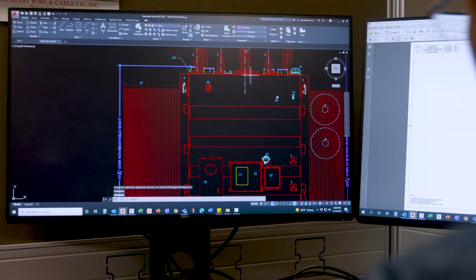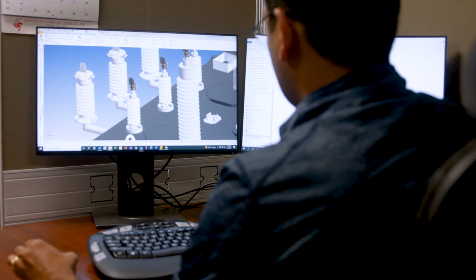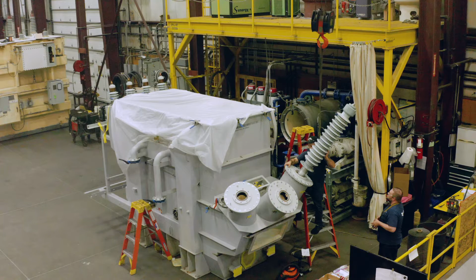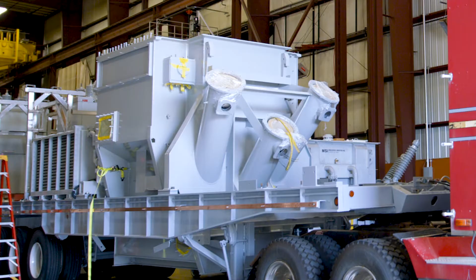We use state-of-the-art design programs while we're redesigning it, so it's basically a brand new transformer and should last the same as a new one, probably longer than some of the new manufacturers. You can get them returned quicker, and they slide right back into the substation they came out of without having to change overhead lines or anything.